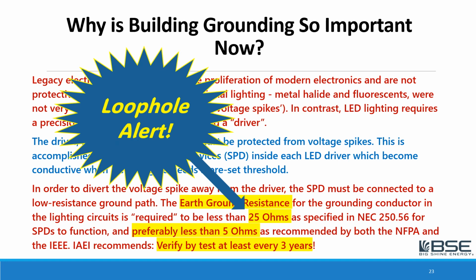But then they put this very strange loophole in there: if you got a reading above 25 ohms, all you had to do was add a second rod a certain number of feet away, but you didn't even have to test it after that. So if you just added a second rod, who knows what you got? You weren't required to test it.